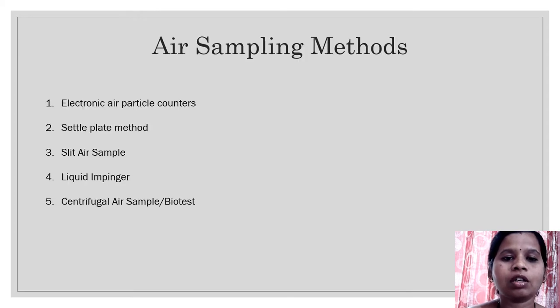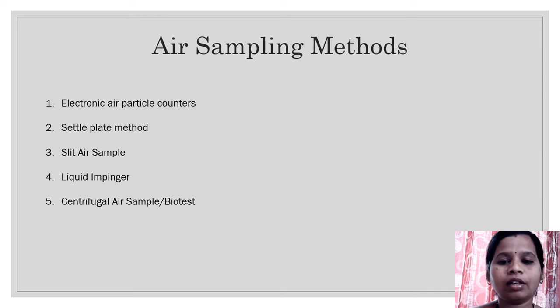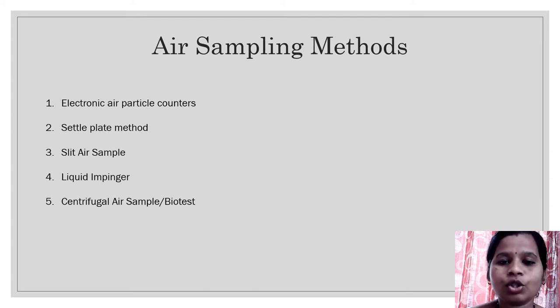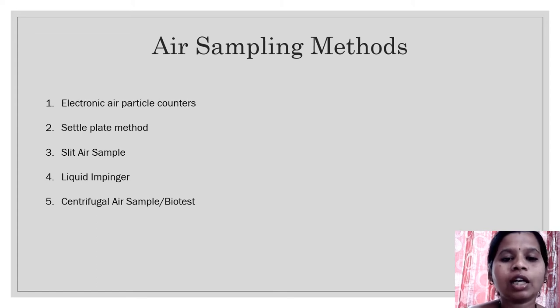In air sampling, the very first method is the electronic air particle counter. These counters are specifically used to determine the number of particles or microbes, counted per cubic feet, and classify the cleanliness of a particular room or area. However, electronic counters can count air particles and microbes but cannot differentiate between viable and non-viable microorganisms, so we need to use other methods for that purpose.